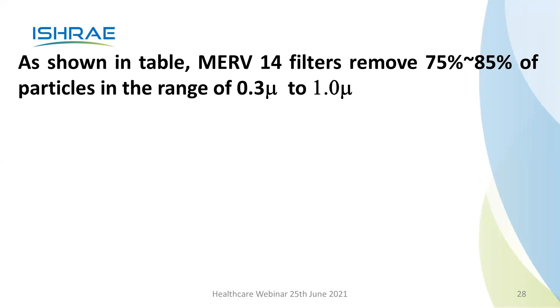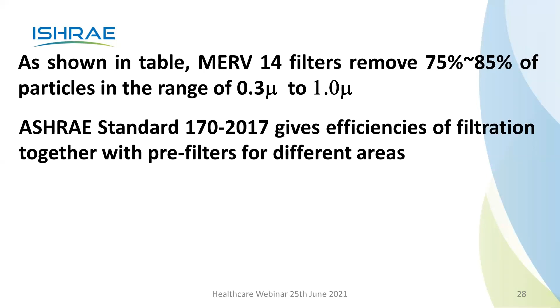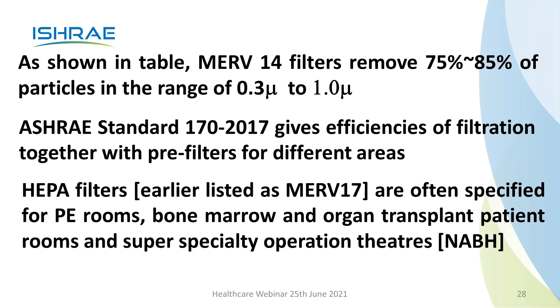MERV 14 removes 75 to 85% of the particles in the range of 0.3 to 1 micron. Standard 170 2017. Now, of course, this is dated. Now, the 21 has also come. It gives efficiencies of filtration together with pre-filters for the various different areas. HEPA filters, earlier listed as MERV 17, are often specified for PE rooms, bone marrow, organ transplant patient rooms, and super specialty operation theaters. This is where the HEPA filters are used. In most of the critical areas, it is enough to use MERV 14, which I told you is 75 to 85% for 0.3 to 1 micron. You don't use HEPA filters everywhere. And other areas, less critical areas, you can do with MERV 8 and things like that.